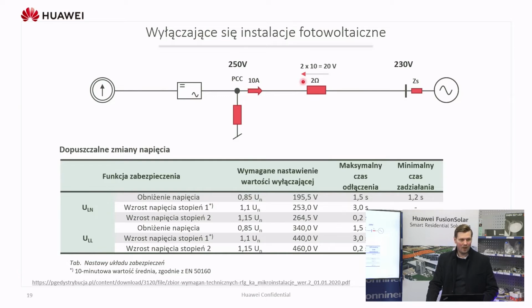So if the grid quality is not good enough, the inverter will raise the output voltage above the allowed limit, which is 253 volts. And it's usually said the inverters are faulty because we have overvoltage, which is like 50% of the truth. The inverter is rising the voltage slightly, but only as much as the line impedance is forcing it to.